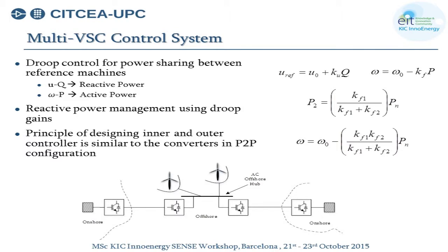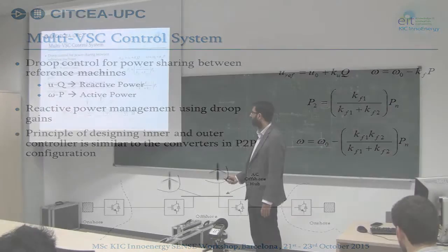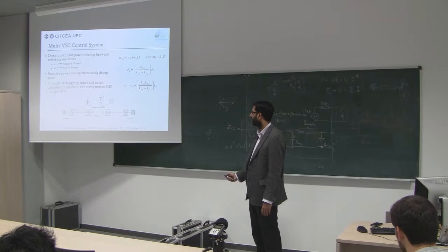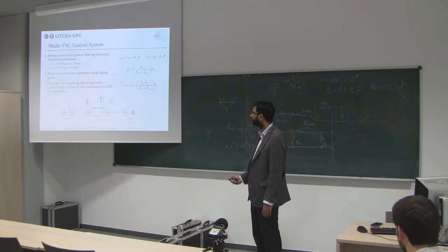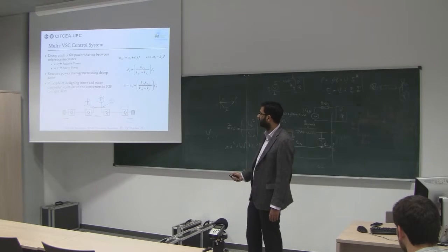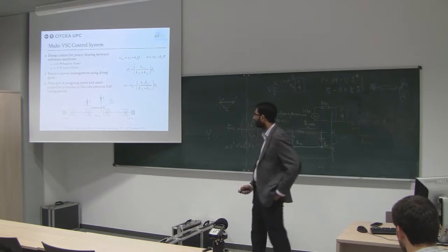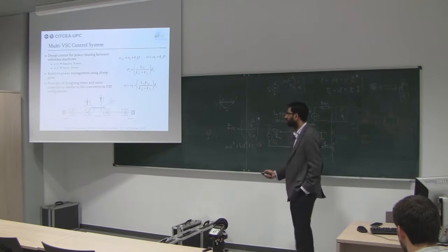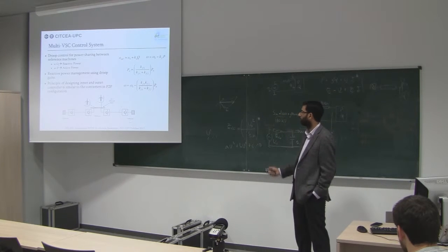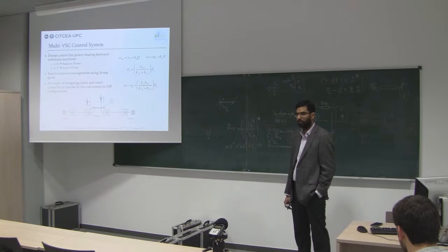One possibility is the multi-VSC control system, like a multi-infeed system. If you see this structure, both converters are connecting to the same offshore network, but they have a point-to-point configuration. So we don't need a DC circuit breaker here, and the grid frequency is provided by both converters. If one transmission system goes out, you can still operate the network. So the principle is designing the internal control system based on point-to-point. There are already many HVDC point-to-point connections that exist.